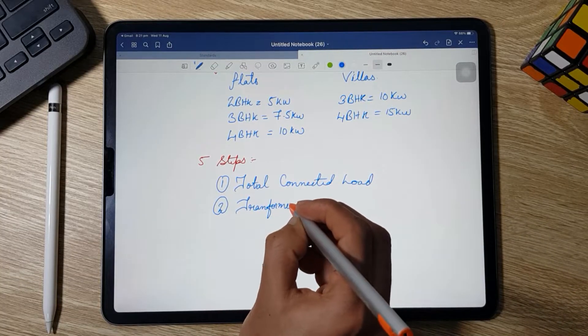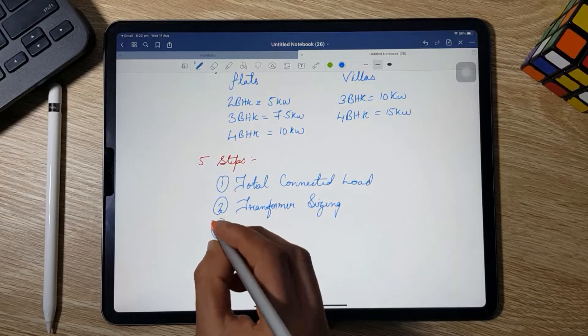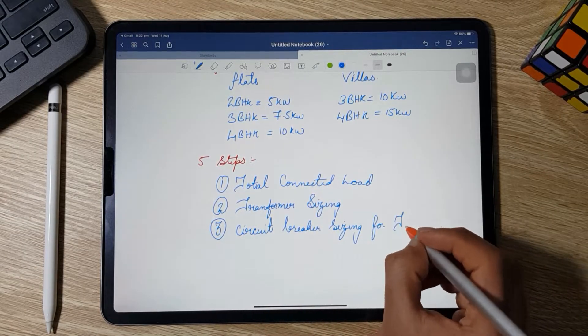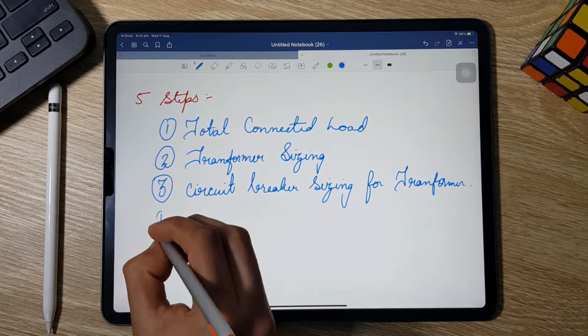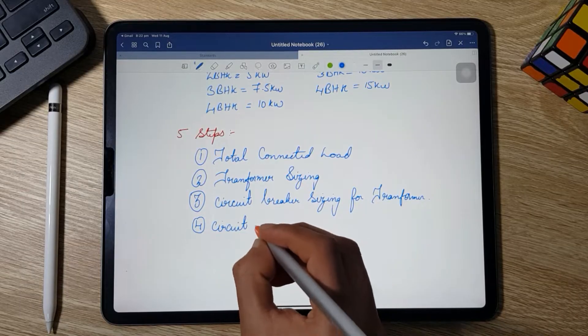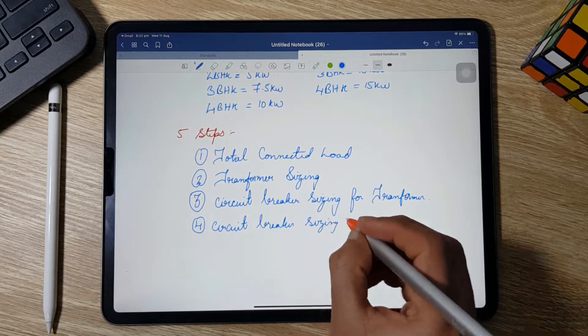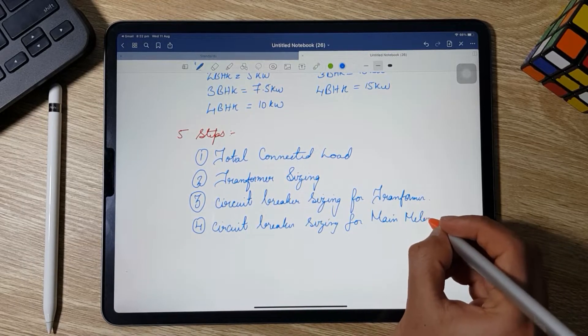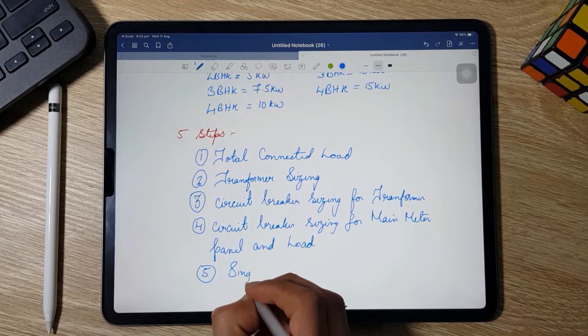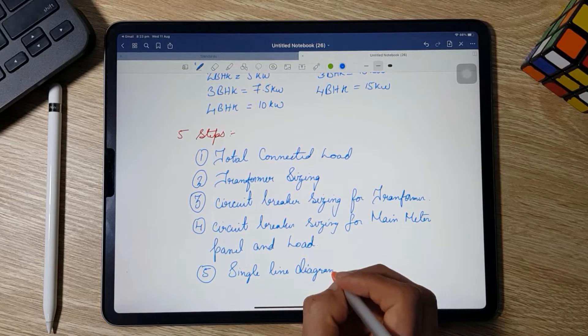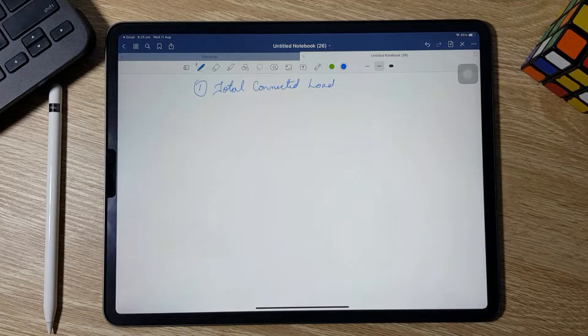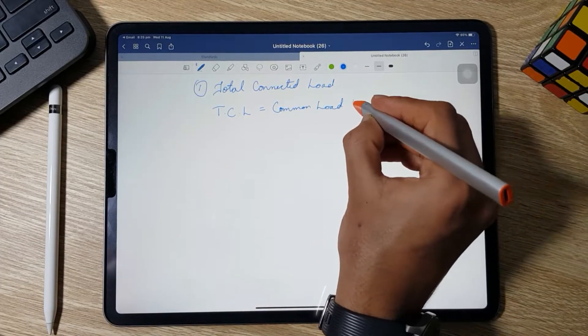Now let's start working on the main idea of this video, which has 5 steps. Step 1 is total connected load, Step 2 is transformer sizing, Step 3 is circuit breaker sizing for the transformer. The main difference between designing a normal building and a high-rise building lies in Steps 4 and 5. Step 4 is circuit breaker sizing for the main meter panel and loads, and Step 5 is the single line diagram.